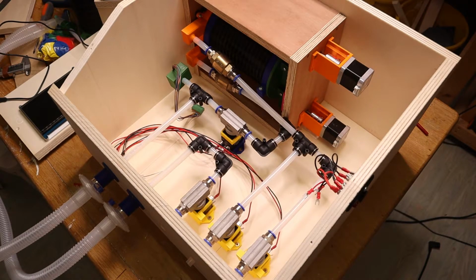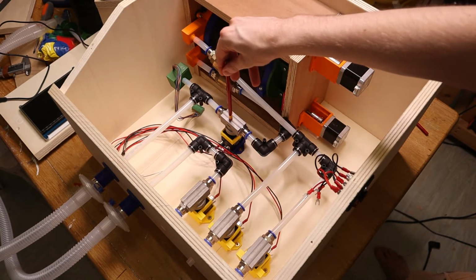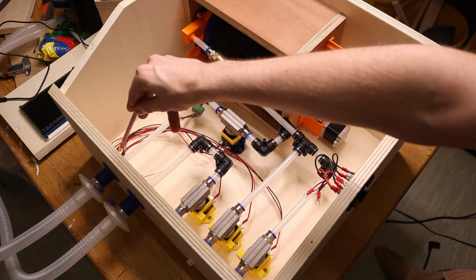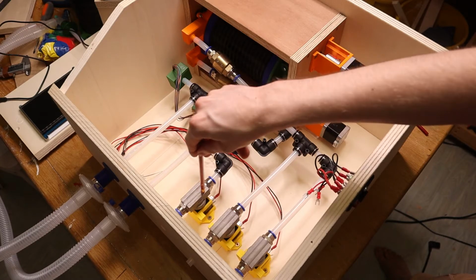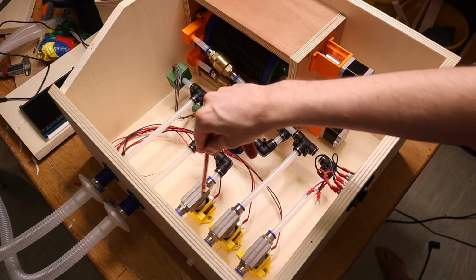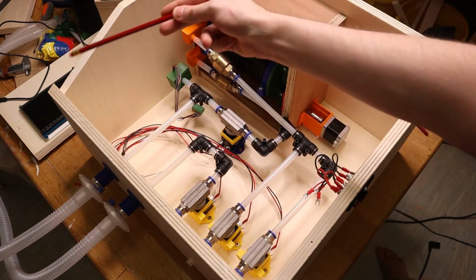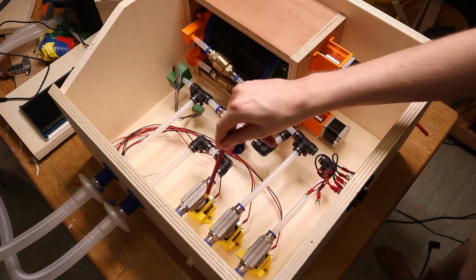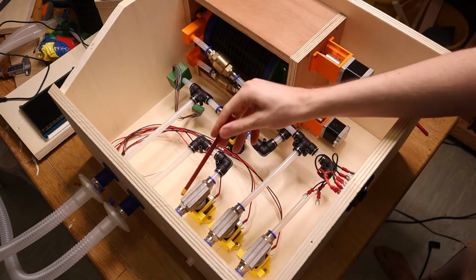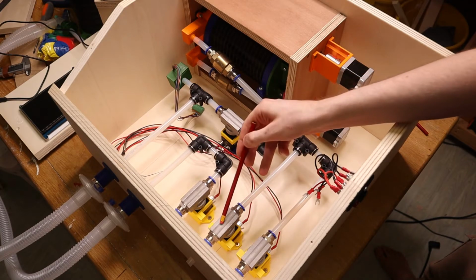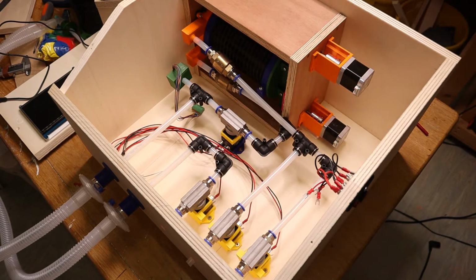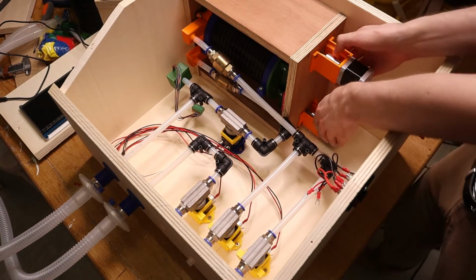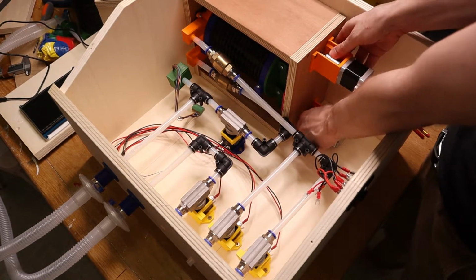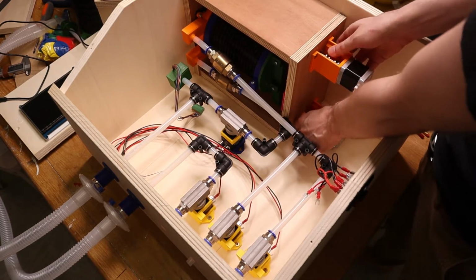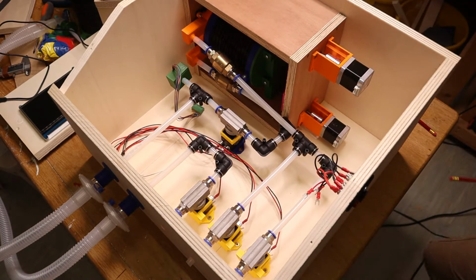So what would a cycle look like? Well, to start the inspiration, you open up this valve so that the air from the bellows can actually make its way into the patient. You have this valve closed to ensure that whatever air you push into the patient doesn't immediately come back out again. In that case, this would basically just be a leak and you're pushing air right out of the system here. And both of these valves for the inputs can be closed. So the way you start is by turning the bellows pump like this. So both of these stepper motors go at it. And that is basically an inspiration.